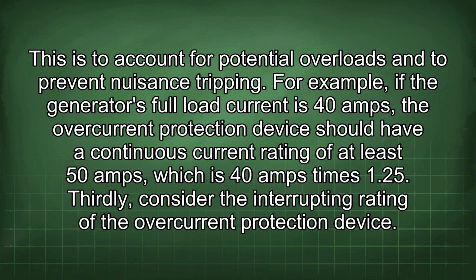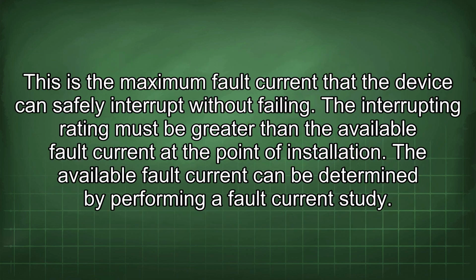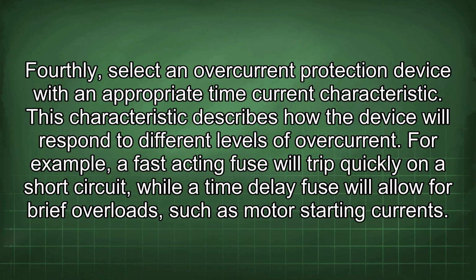Thirdly, consider the interrupting rating of the overcurrent protection device. This is the maximum fault current that the device can safely interrupt without failing. The interrupting rating must be greater than the available fault current at the point of installation. The available fault current can be determined by performing a fault current study. Fourthly, select an overcurrent protection device with an appropriate time current characteristic. This characteristic describes how the device will respond to different levels of overcurrent. For example, a fast-acting fuse will trip quickly on a short circuit, while a time delay fuse will allow for brief overloads, such as motor starting currents.